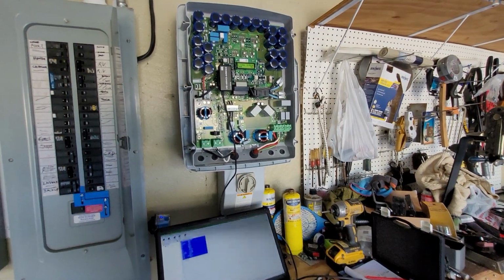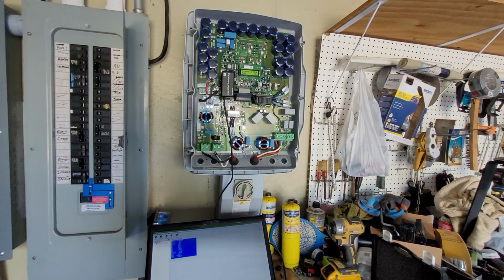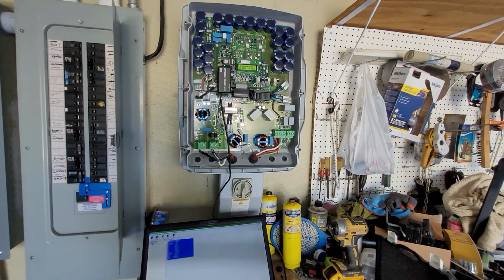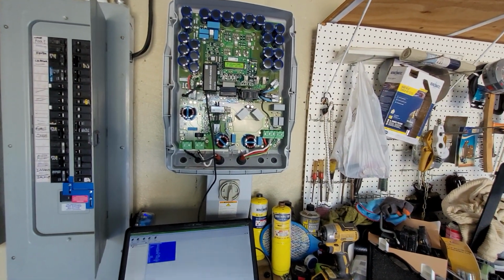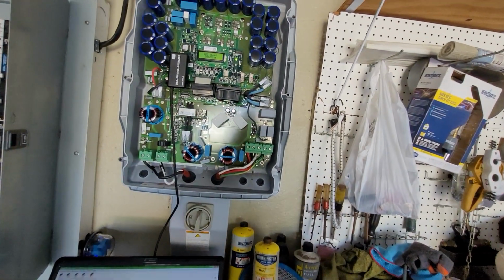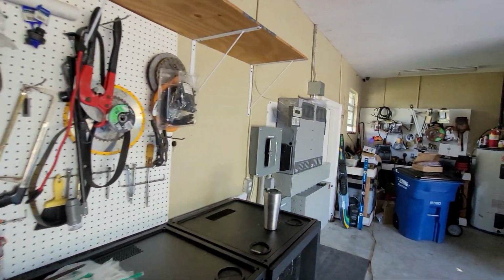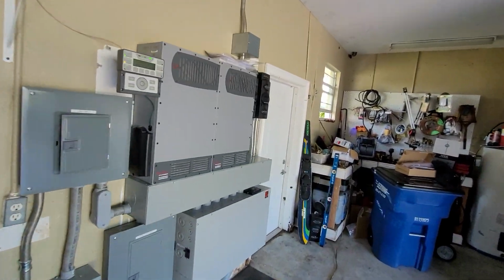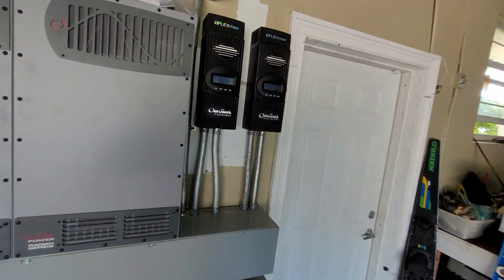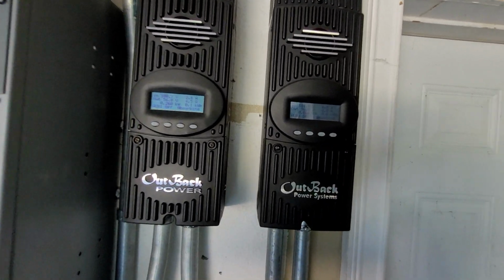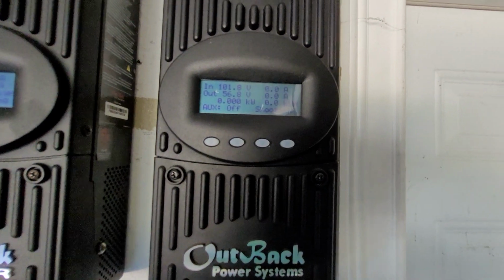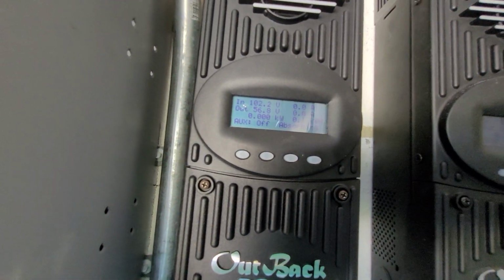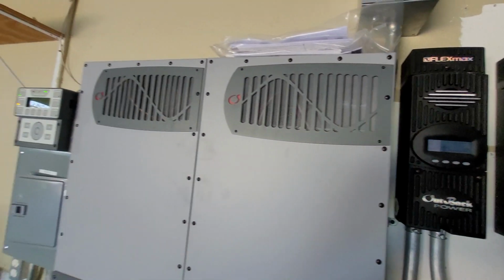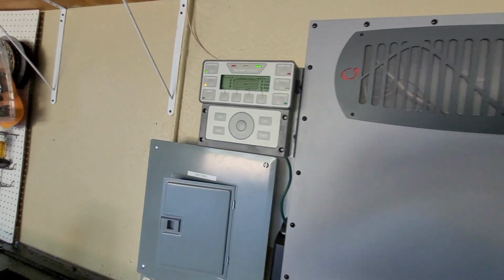I can't remember what he said this was. I think it's a 13 kilowatt array on this inverter. It might have been a 15 kilowatt array on this 10,000. And then it's got a 5 or a 6 kilowatt array on these two charge controllers. And they're basically doing nothing because I got them set just a hair lower than the target voltage for these inverters. That way the grid tie inverter does all the work.